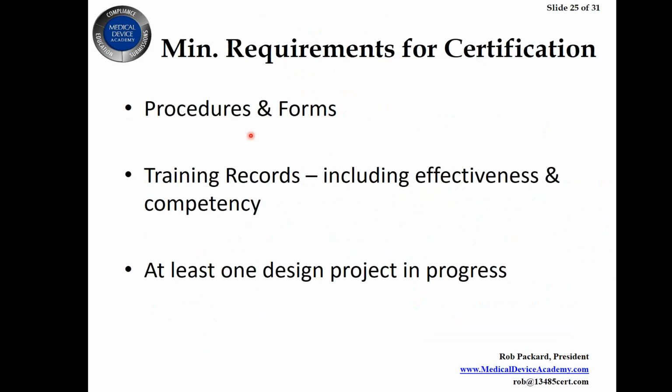Minimum requirements for certification. So this would be certification of your design control process. You may be getting ISO certified before you actually have finished your first design project. And in that case, you need to give them something to look at, otherwise you won't get certified. But you don't have to have a complete design done. A lot of companies are doing it prior to getting their product in a clinical study.